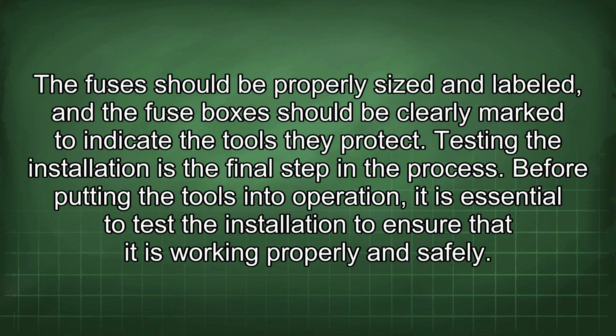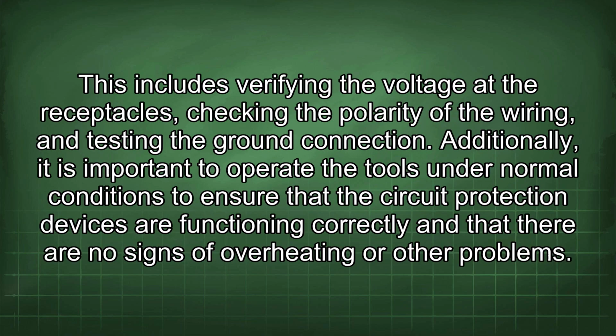The fuses should be properly sized and labeled, and the fuse boxes should be clearly marked to indicate the tools they protect. Testing the installation is the final step in the process. Before putting the tools into operation, it is essential to test the installation to ensure that it is working properly and safely.